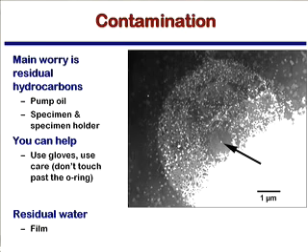In particular, this is a problem for analytical microscopy. If you're trying to do small probe work for EDS or EELS, and you put a very intense probe on your sample, it will actually collect the local carbon around there and form a little tower of carbon. And so if you're starting to do quantitative analysis, you will find that your signal yield changes with time because increasingly what you're probing is the carbon contamination. The sample area is fixed, but the carbon contamination grows, and so you end up having more and more problems with carbon contamination affecting your results. So it's, again, important to be clean.